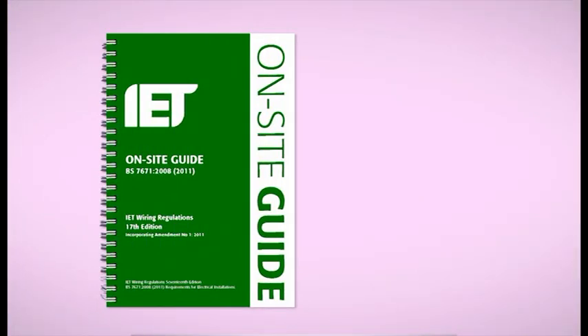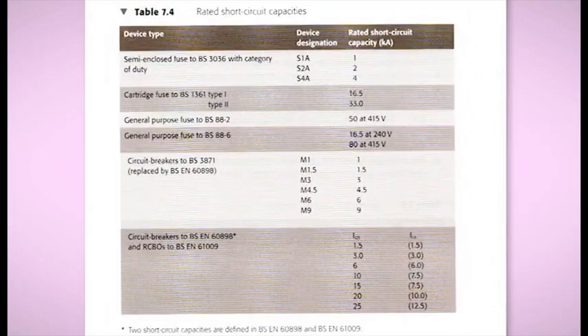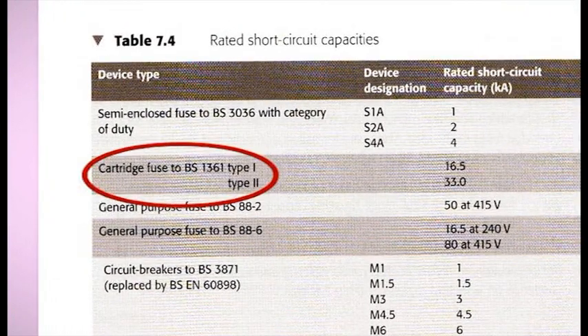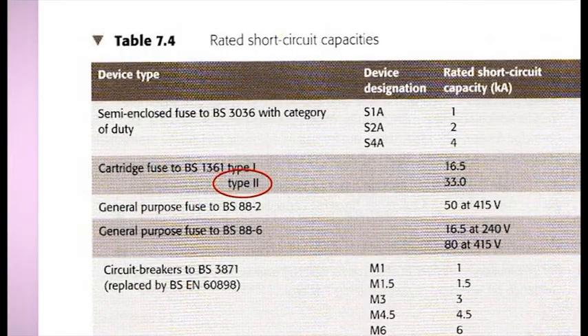fuse. For new installations, it should not be a problem determining the characteristic of the device, but for an EICR, it can often be difficult to ascertain, and in some situations will have to be an agreed limitation of the report. The next box says type. Now I've seen this filled in as new one or grey one, but what it's actually referring to is the type of the characteristic of the device. There is data available to help you determine the type of device in the On-Site Guide. For example, a BS 1361 fuse used as a primary supply overcurrent protective device will be type 2.